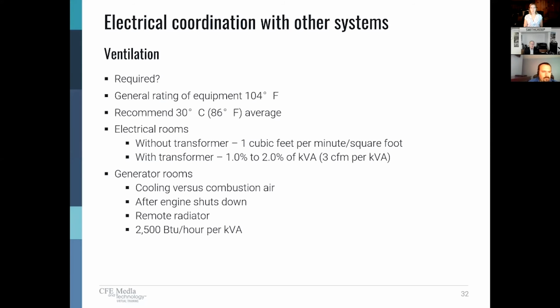So where's the heat coming from? It's coming from the transformers, as I mentioned. There are some rough rules of thumb. Use this in the beginning planning stages, but please get the cut sheets from your actual vendors as you're specifying this. Without a transformer, you can put in about 1 cubic foot per minute per square foot. When you have a transformer, 1 to 2% of the kVA is rejected into heat. Now they're getting more efficient these days, but 3 CFM per kVA. Again, these are rough rules of thumb.